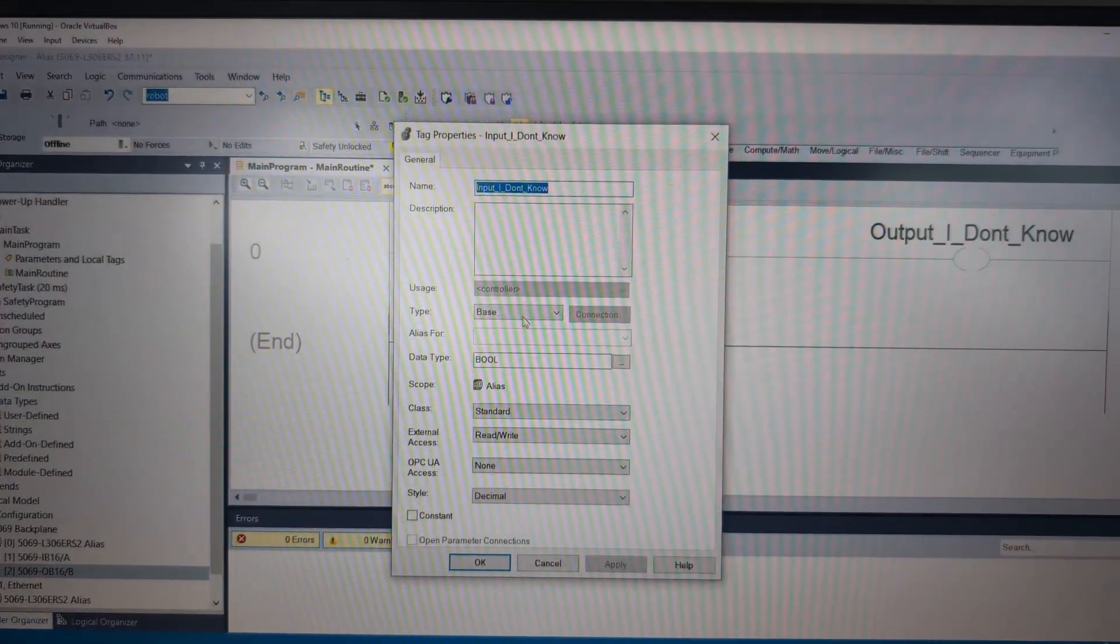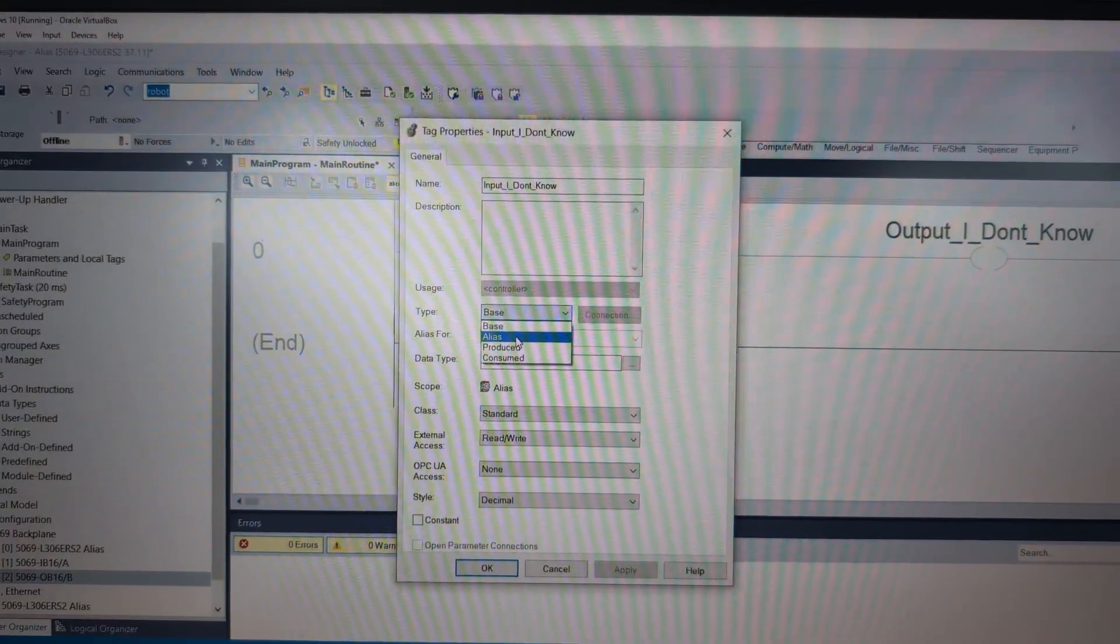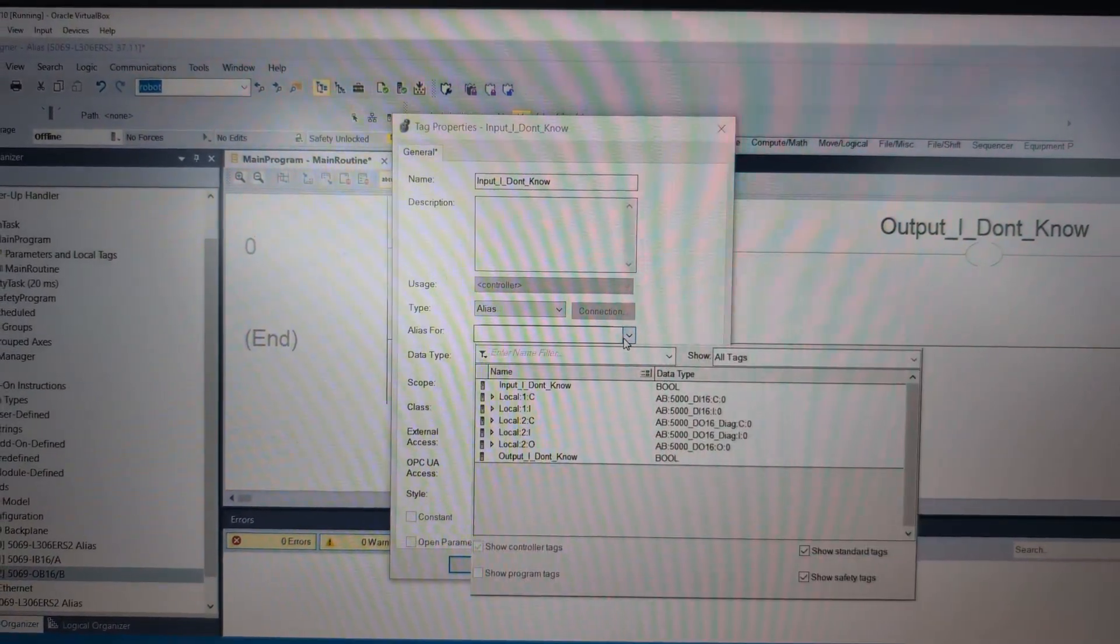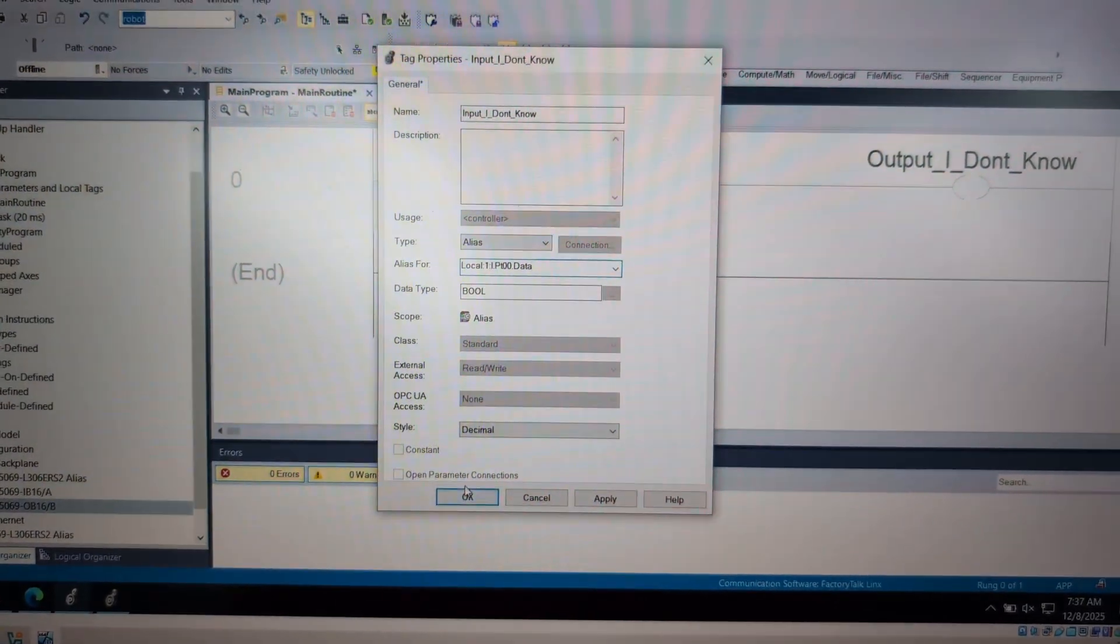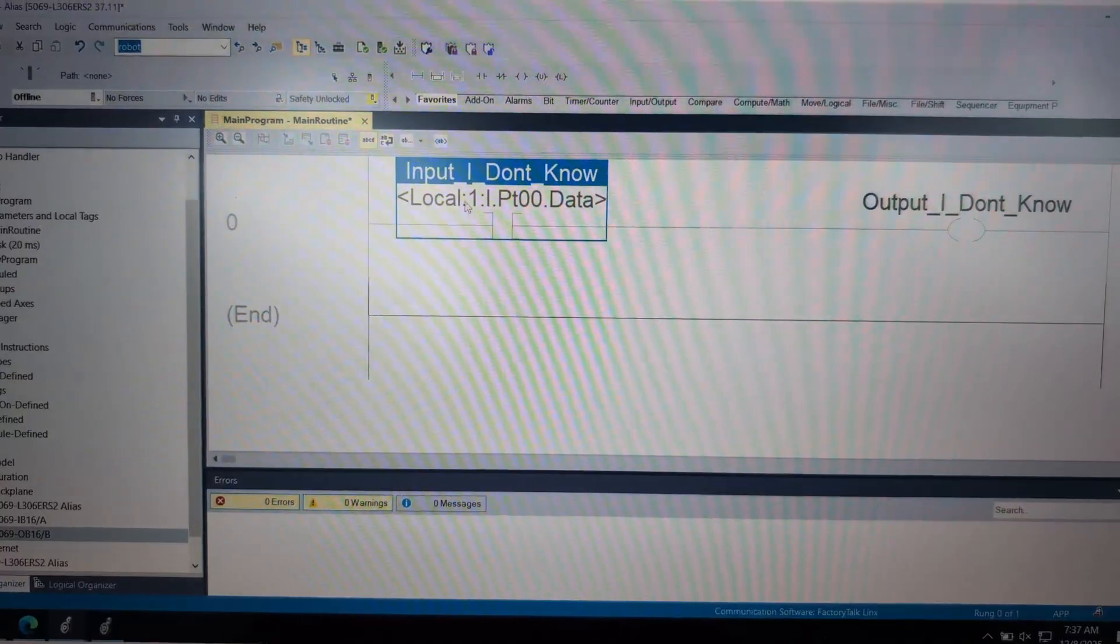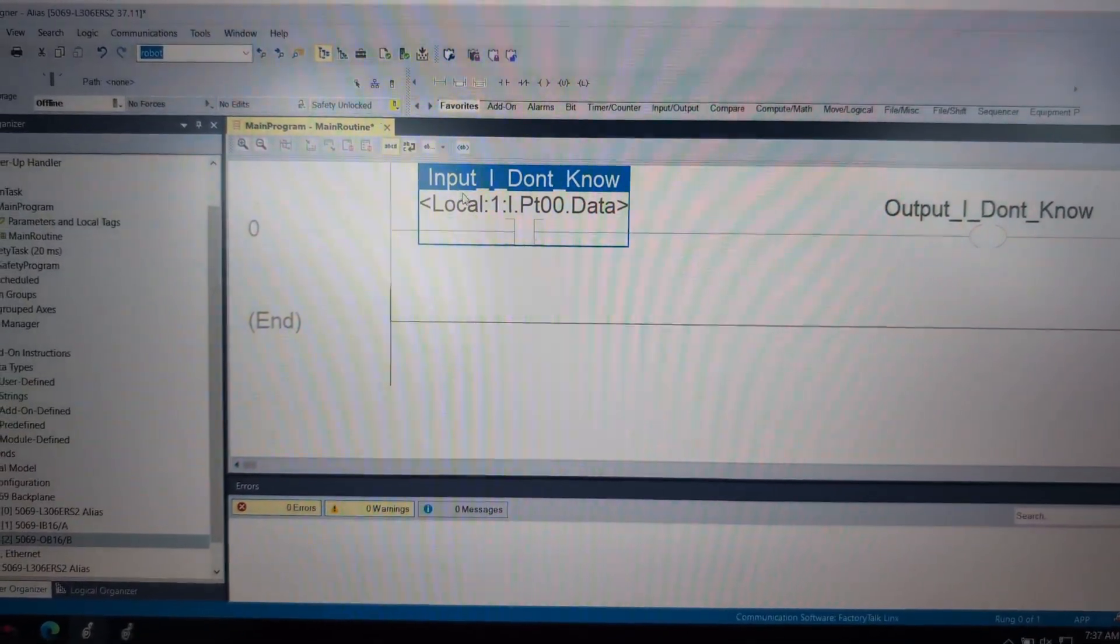But what an alias is, is under this type, we can select alias. And then directly beneath it, alias for, then we would go find local:1:I, and let's just say its I/O assignment was PT00.data. And then we can hit create on it. And we get a nice little description beneath it.